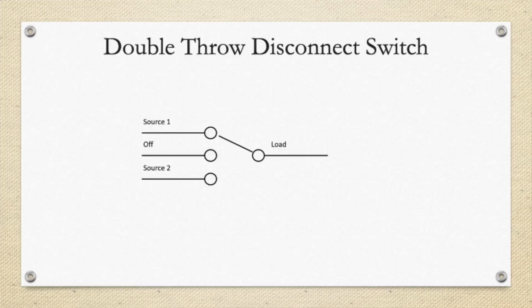Going to diagram number 1, we're showing a double throw disconnect. This is probably the least expensive maintenance bypass we've seen over the years. It's a double throw switch that you can put 2 sources into, and the output of that switch is going to feed your critical load. What's the disadvantage to this? It's a break before make. So in the event you have a failure on your UPS, yes, it's a way to reroute power to your critical load, but there will be an interruption in getting over to that secondary source.